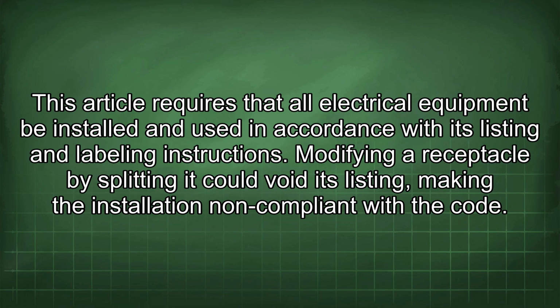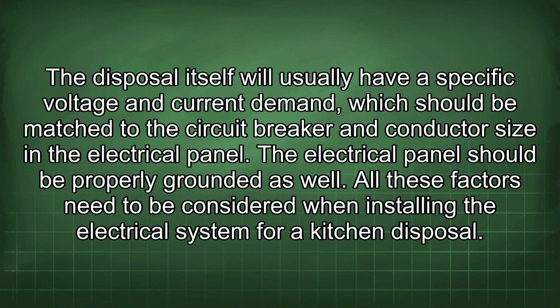This article requires that all electrical equipment be installed and used in accordance with its listing and labeling instructions. Modifying a receptacle by splitting it could void its listing, making the installation non-compliant with the code. The disposal itself will usually have a specific voltage and current demand, which should be matched to the circuit breaker and conductor size in the electrical panel. The electrical panel should be properly grounded as well. All these factors need to be considered when installing the electrical system for kitchen disposal.